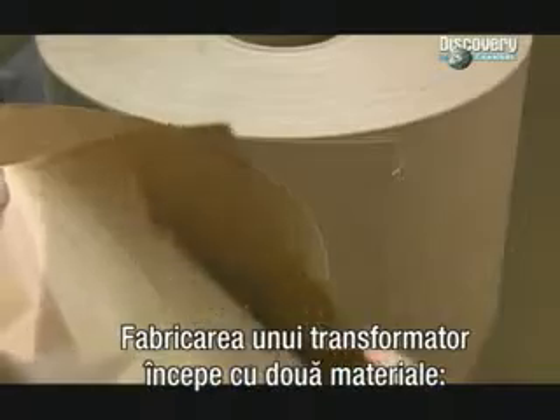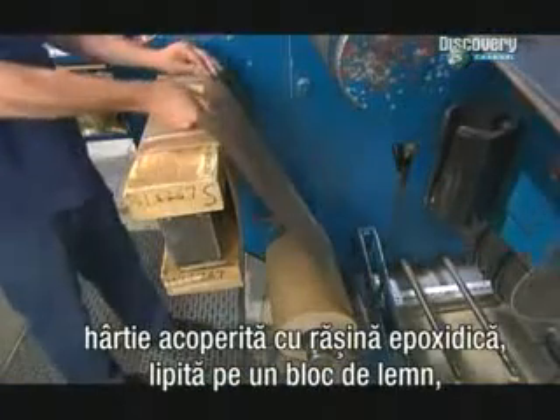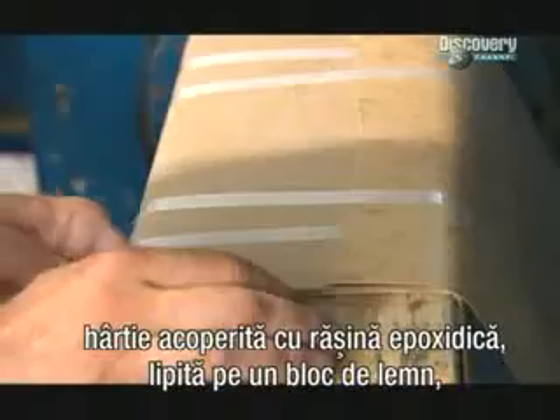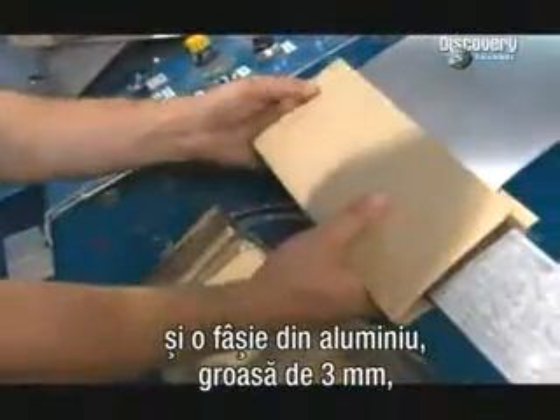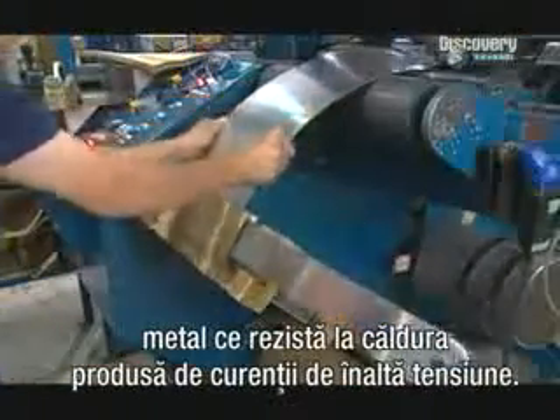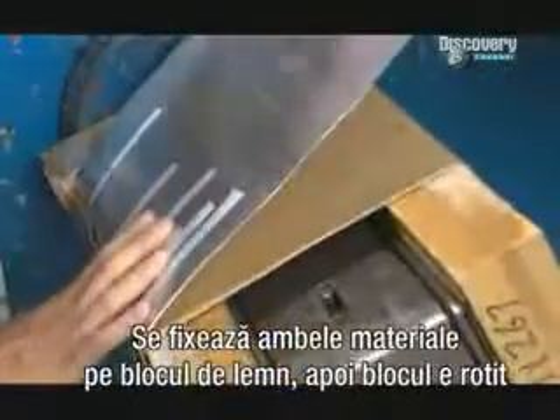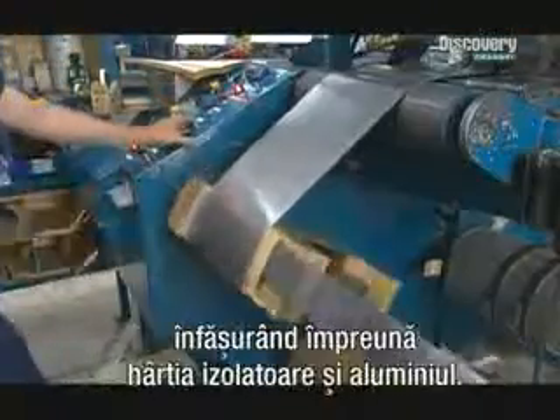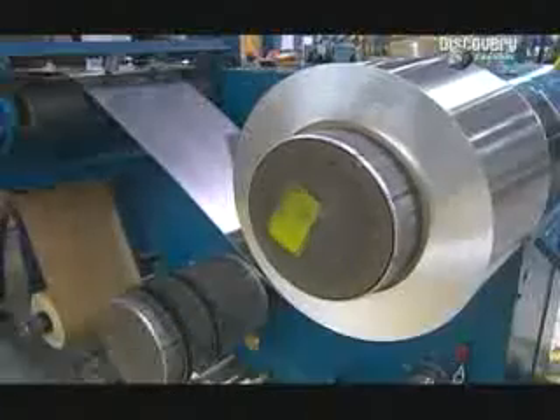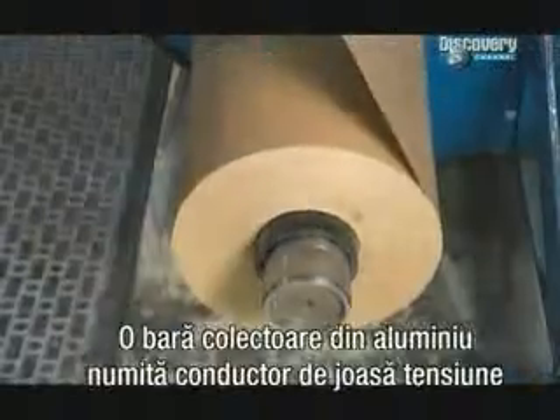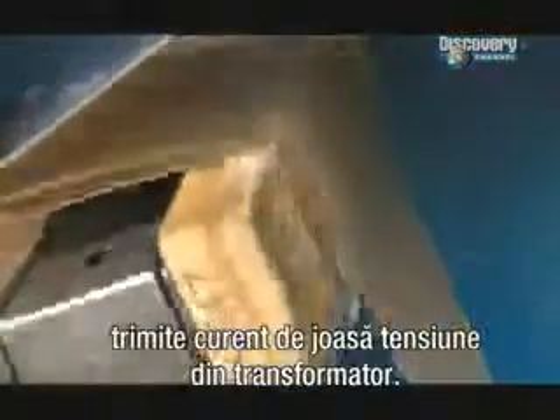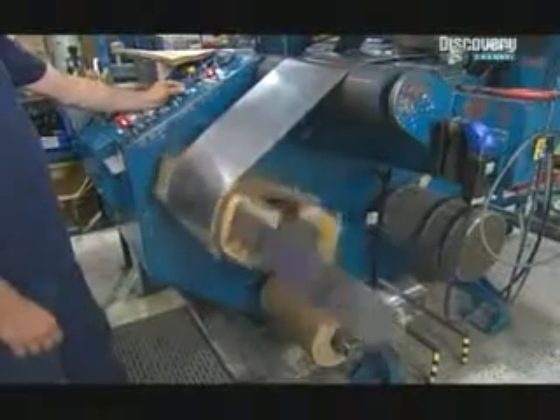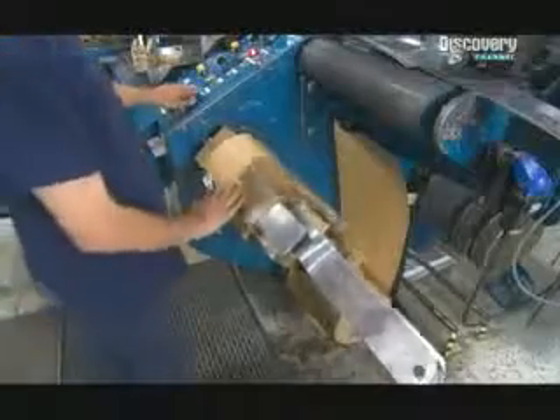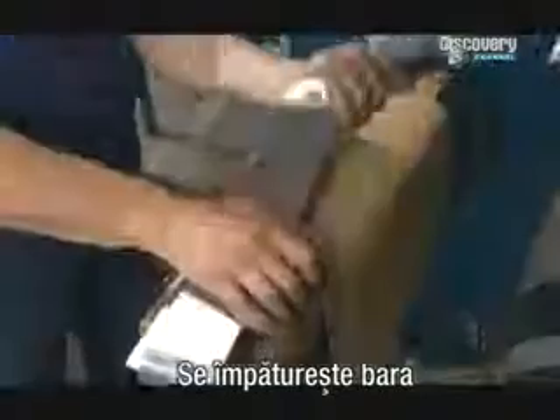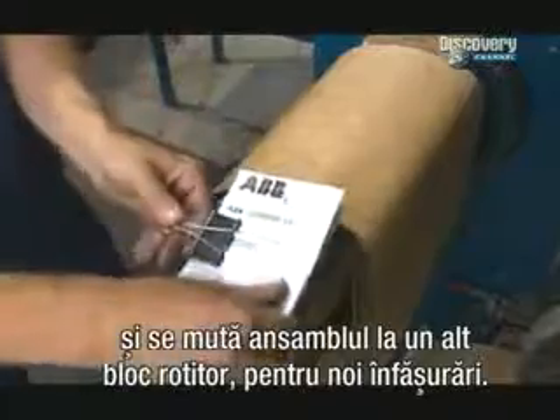To make a transformer, they start with two materials: paper that's coated with epoxy glue taped to a wooden block, and a 3mm thick aluminium strip, a metal that withstands the heat a high voltage current produces. They secure both materials to the block and rotate it, wrapping the insulating paper and aluminium together. An aluminium bus bar, called the low voltage lead, sends low voltage current out from the transformer. They fold the lead and move the unit to another rotating block for more wrapping.